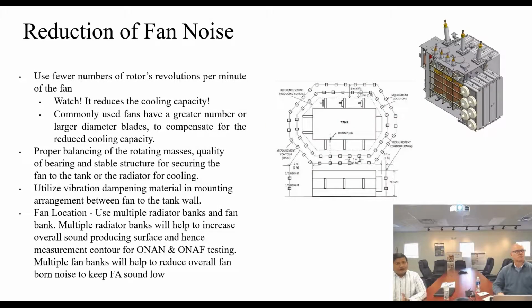So, reduction of the fan noise. Fan noise reduction can be achieved with fewer rotor revolutions per minute. That means reducing the RPM or speed of the fan. But that adversely affects the transformer cooling, as we have less CFM, or less amount of air. So that means the effective cooling has been reduced. And in order to compensate for that, we either need to use more fans, or increase the size of the blades so that they can cover more area, and with the lower RPM, we can still get the higher CFM.